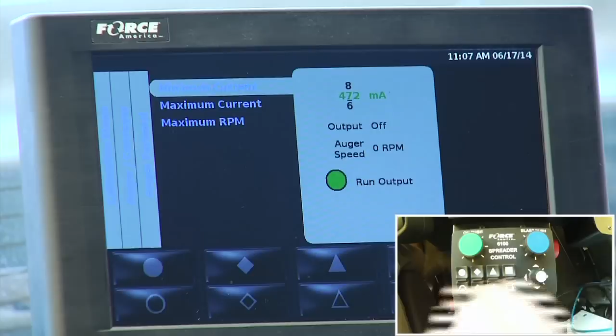That's called my min. Now I'll get out of there for my next setting, which is the max. This is important because I need to saturate my valve, but I don't want more milliamps than necessary since that affects calibration. Right now at 760 milliamps, that's the maximum, and the hydraulic motor turns at 62 RPM.